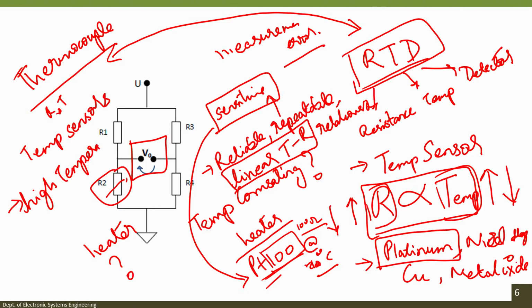So if you want to design an anemometer, to measure the flow of fluid, and it is running at relatively very high temperature, then the choice would be a thermocouple and not an RTD sensor. Another parameter is the thermocouple is highly robust in nature. So what I suggest is go ahead and look at the different available thermocouples in the market, their ratings, the sensitivity, and compare them with the commercially available RTD sensors. That can give you more clarity about how sensitive they are, and based on your application, what choice you can make. Can you use a thermocouple or an RTD sensor?